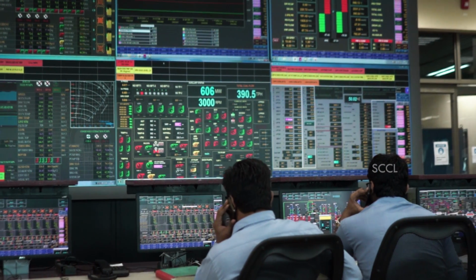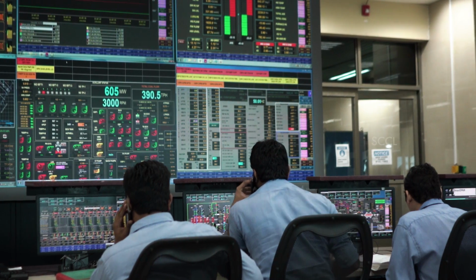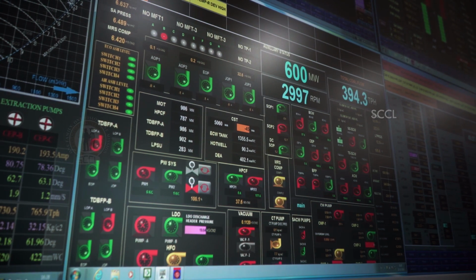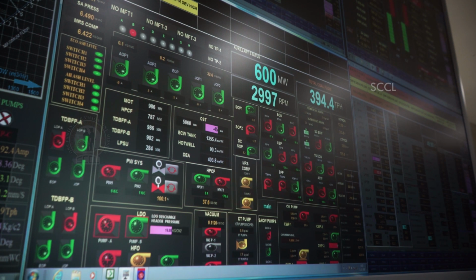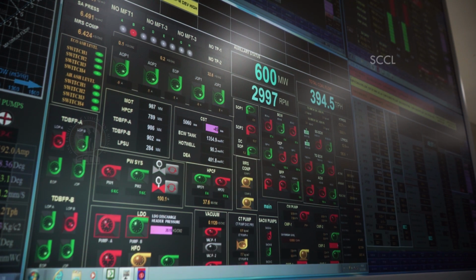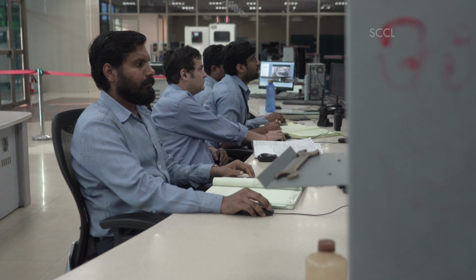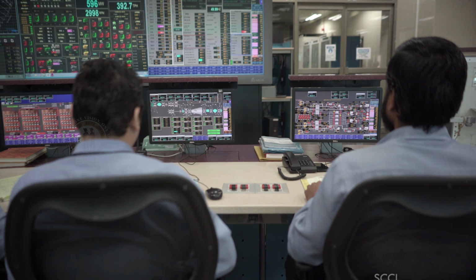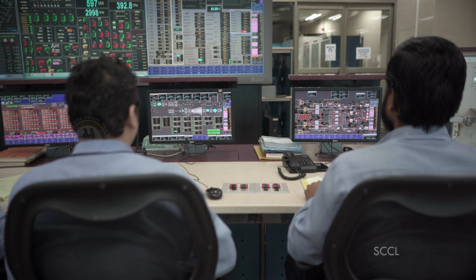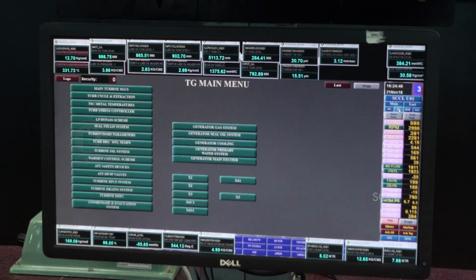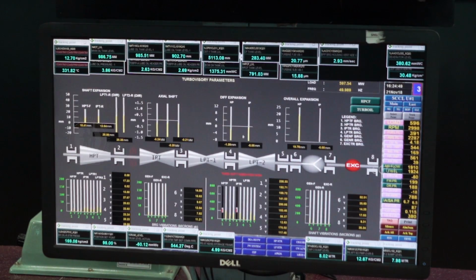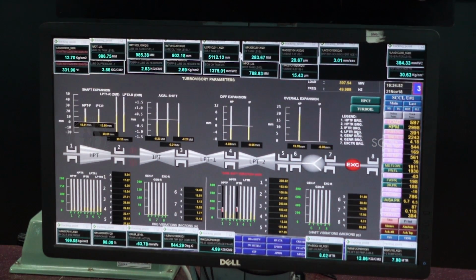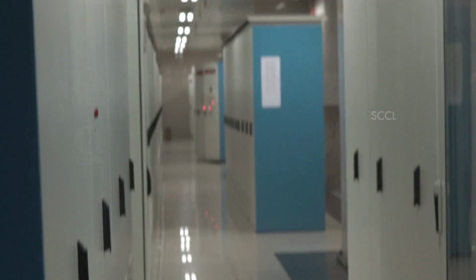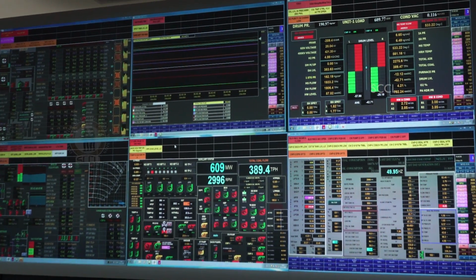All these operations are controlled in a common control room, where each unit has a separate large display video screen which displays all the parameters regarding that particular unit. In each shift, there will be a shift in charge and a minimum of 4 desk operators for each unit who control the boiler, turbine, electrical and water system parameters. All the people in the control room are either electrical or mechanical engineers having knowledge of MaxDNA, a software used by STPP which is made by BHEL's electronics division at Bangalore. The function of the control room is to maintain the system in auto mode as per rated norms.